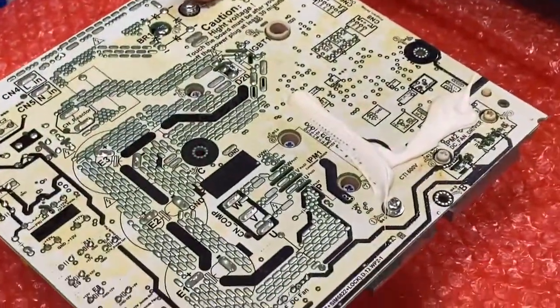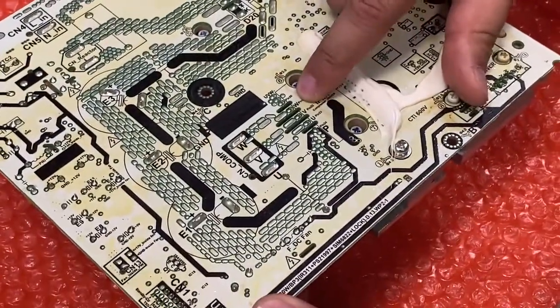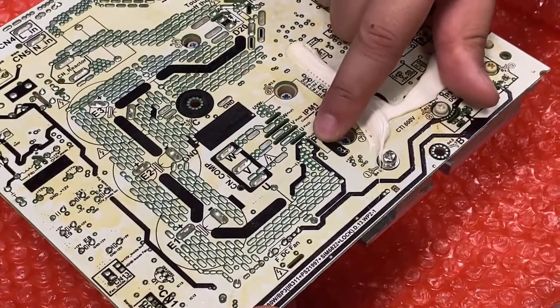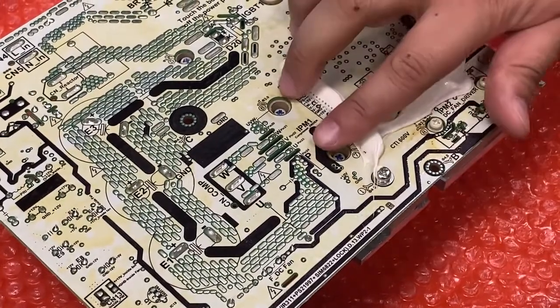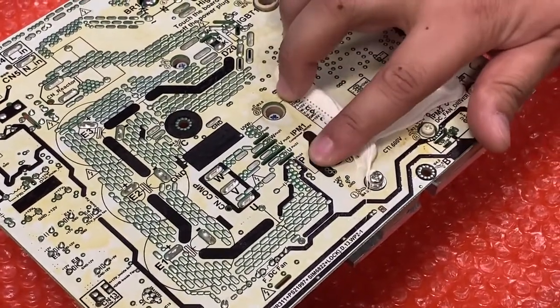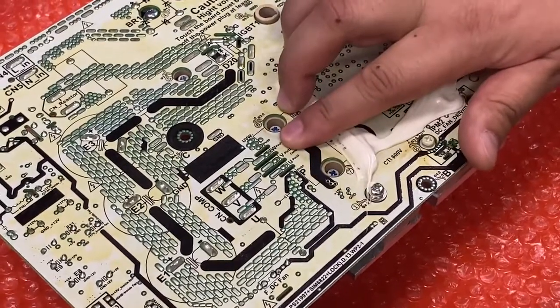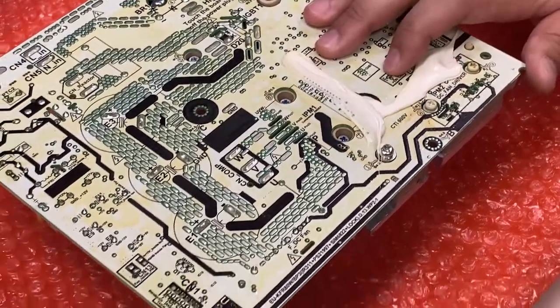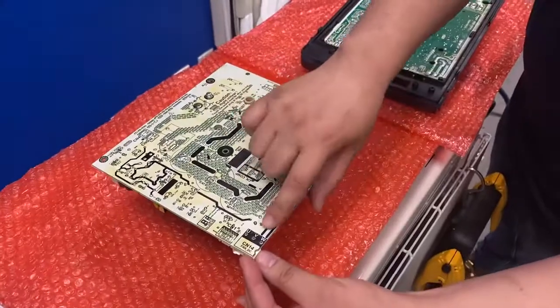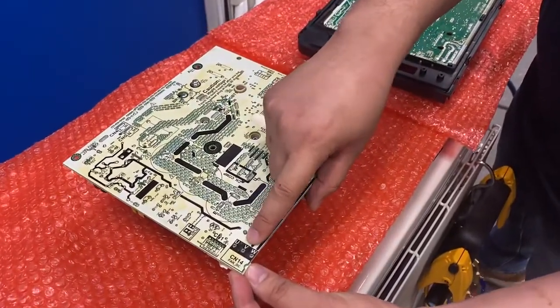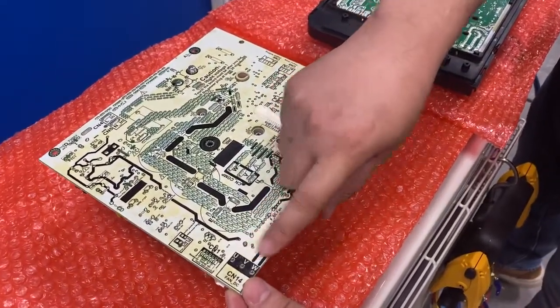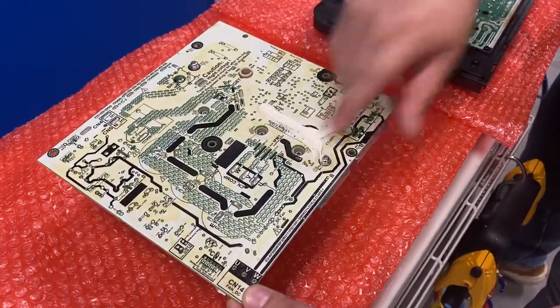You're going to do the exact same thing if it's a standalone IPM board. You're going to locate W, V, U, and P, and check the points between P to U, P to V, P to W. It doesn't matter where on the board you check. For instance, here as well is U, V, and W. You can check between these points to here as well.